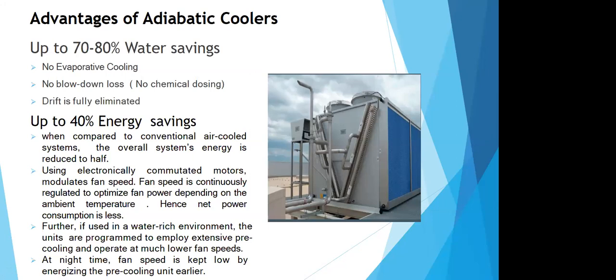Further, if you have a water-rich environment, you can employ and maximize the pre-cooling effect and lower the speed of the fan and the power consumption of the fans. Similarly, in nighttime, one can also reduce the fan speed to a minimum and energize the pre-cooling mode or adiabatic cooling mode to reduce the temperature of the air. So these are various methods through which one can save almost 40% energy compared to a conventional air-cooled system, and almost 80% of water savings as compared to a water-cooled system.